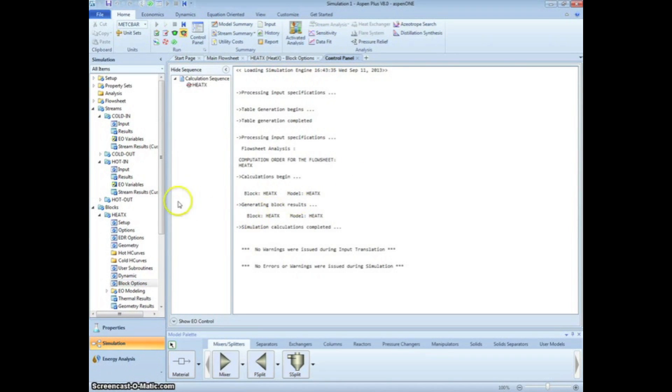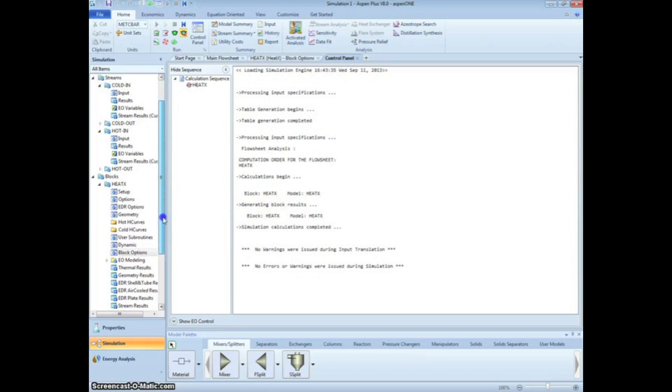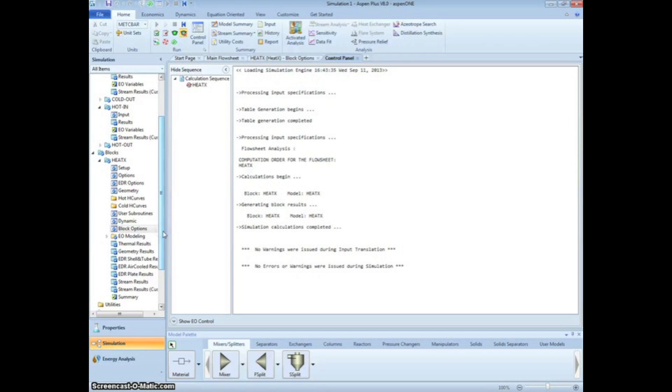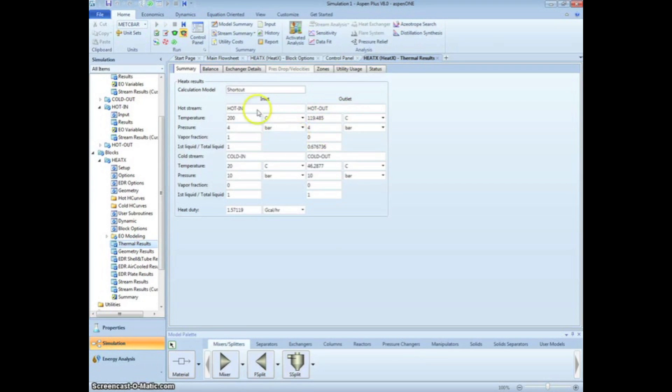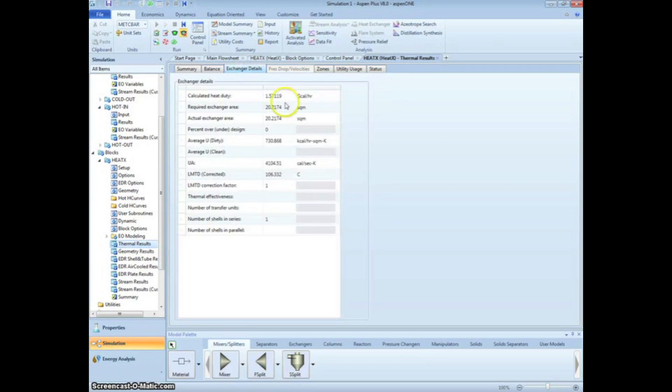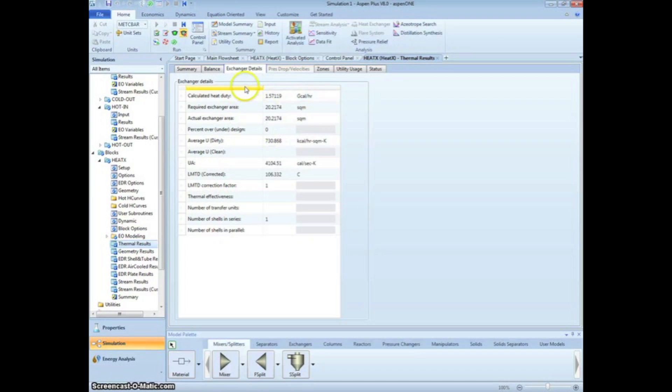To view the results, click on Thermal Results in the menu tree. We see that the hot stream outlet temperature is about 120 degrees Celsius. If we click on the Exchanger Details tab, we see that the area required for heat exchange is just over 20 square meters.